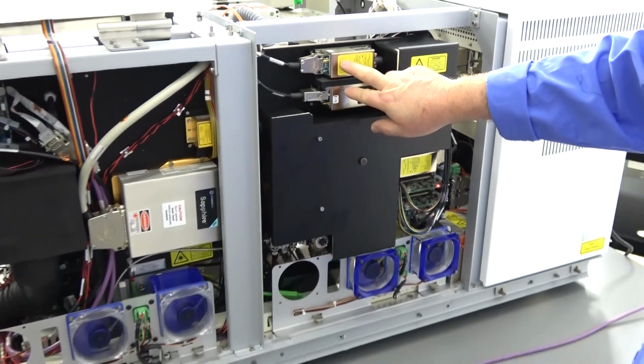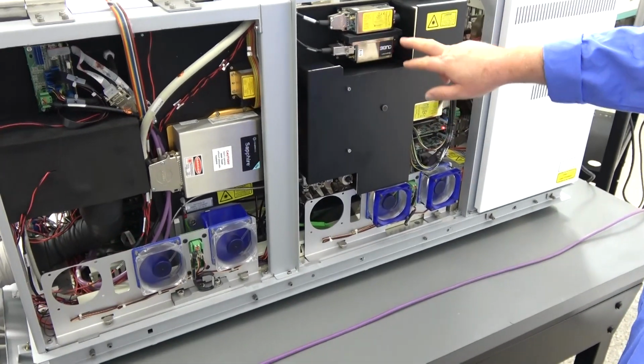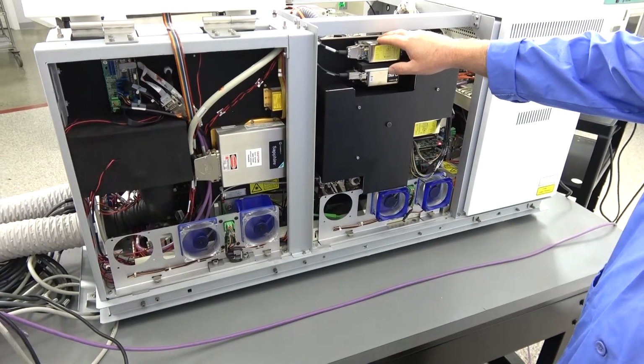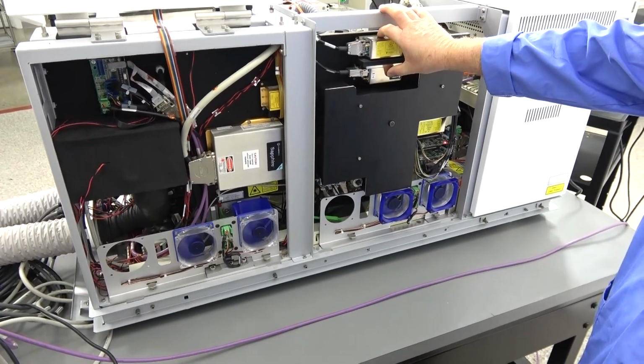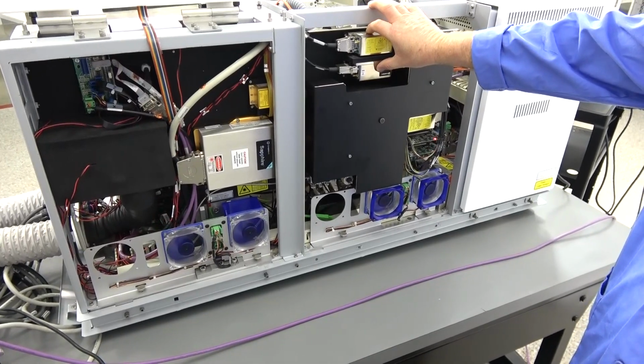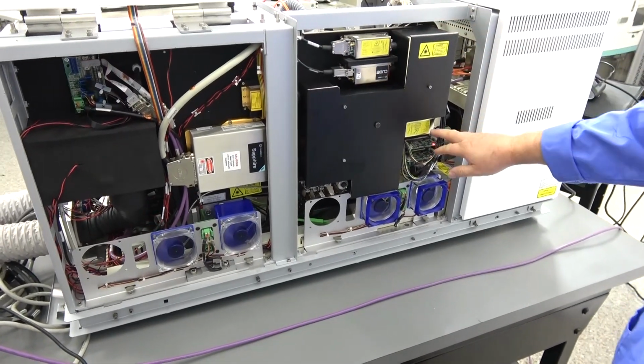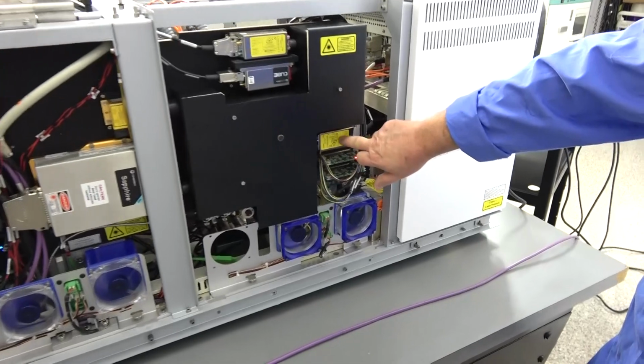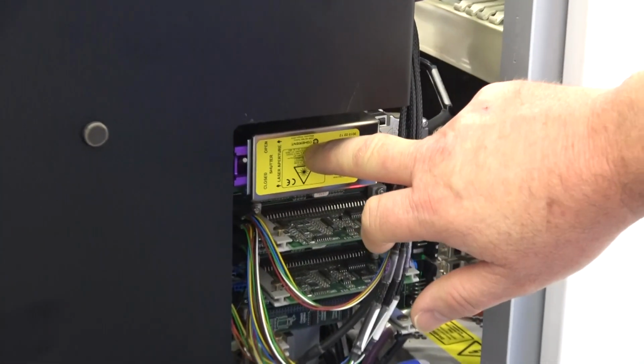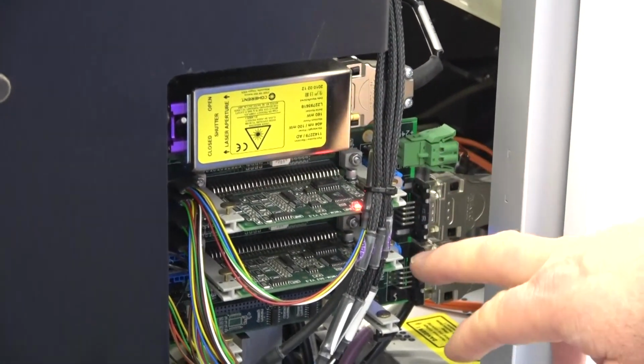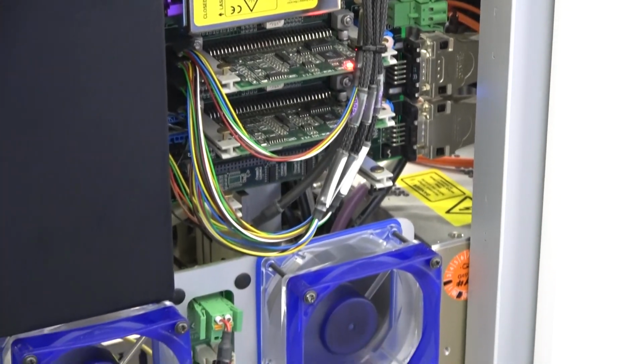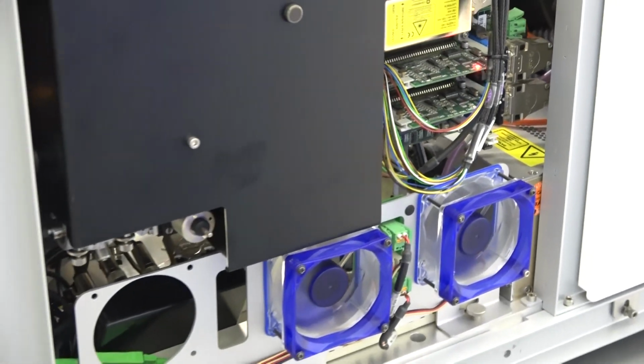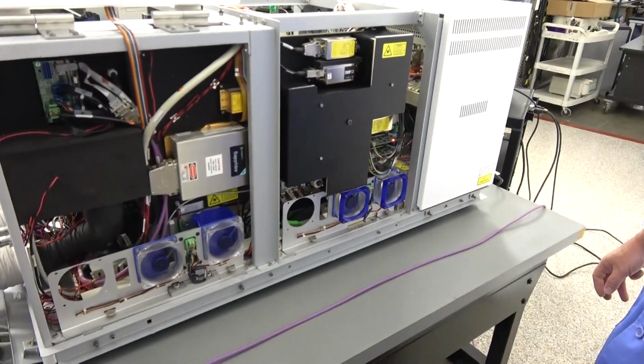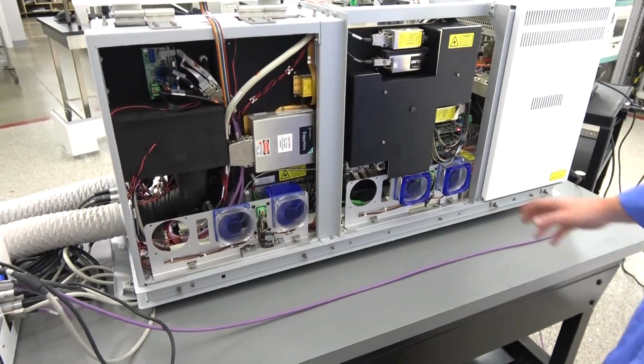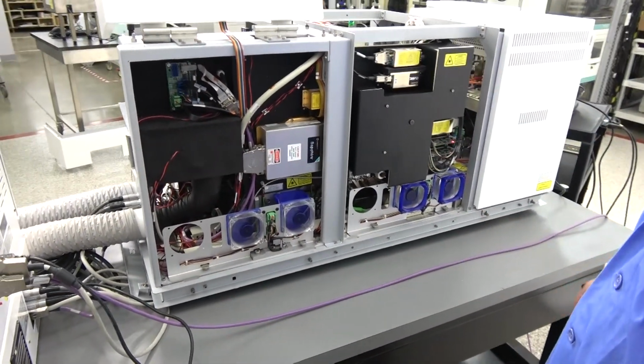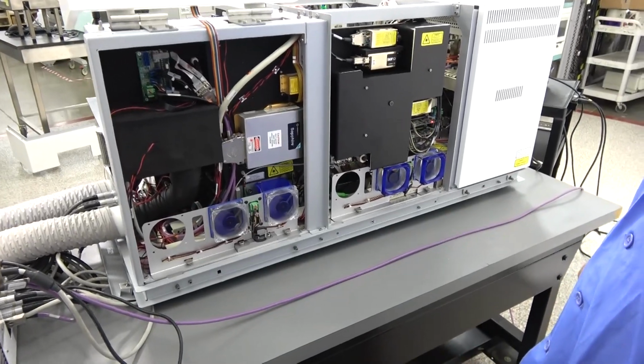Now that's not always an option on some of the Operas out there. Some of them will only have 1 laser, but this one actually has both the red lasers installed. It combines them, and then down here you can also see your violet laser, which is also a Coherent cube laser. And then you have the control cards. But like I said, we have all the spare parts if anything goes wrong with these. I've actually fixed these quite a few times.